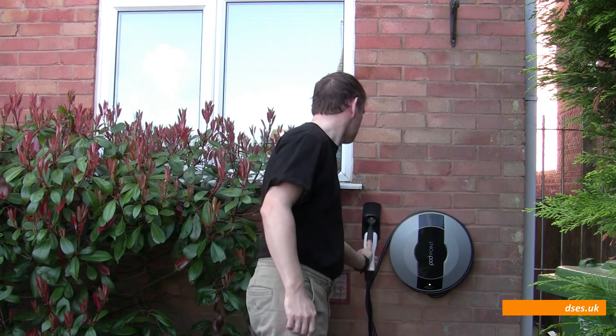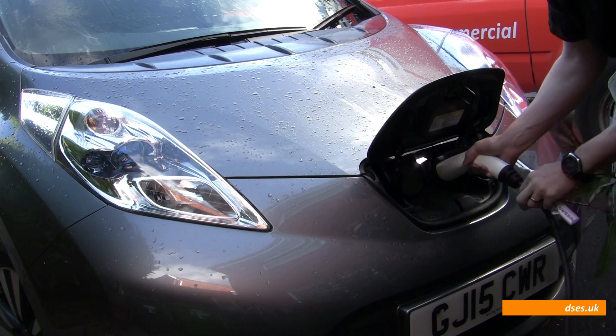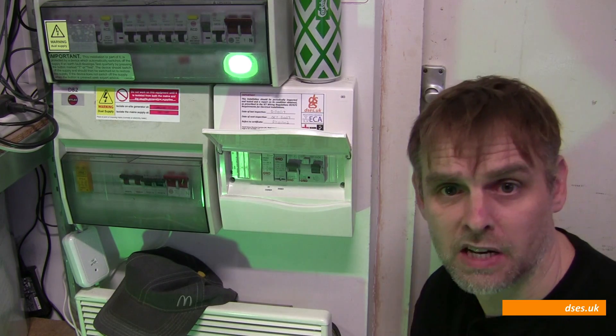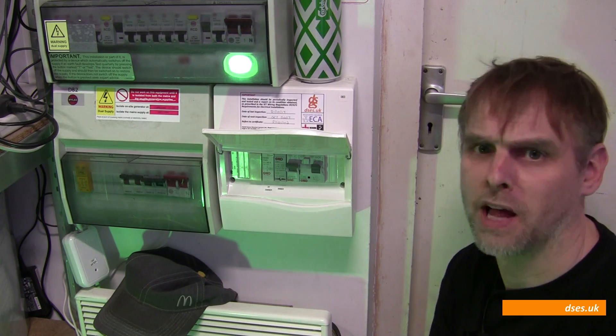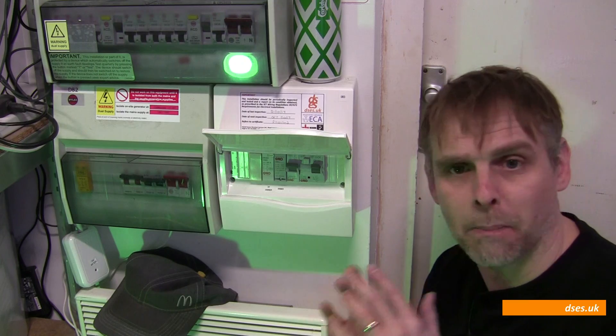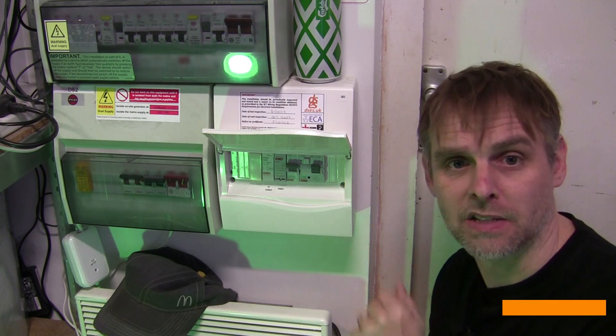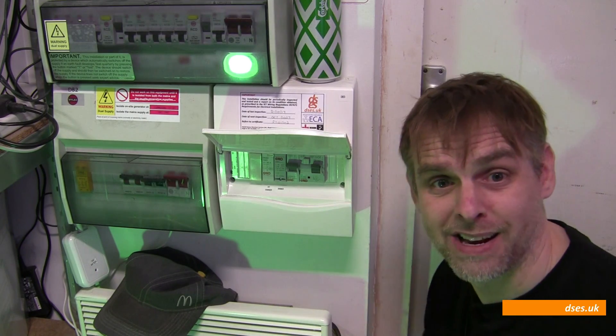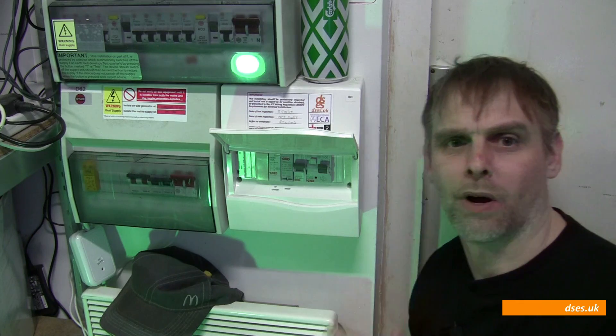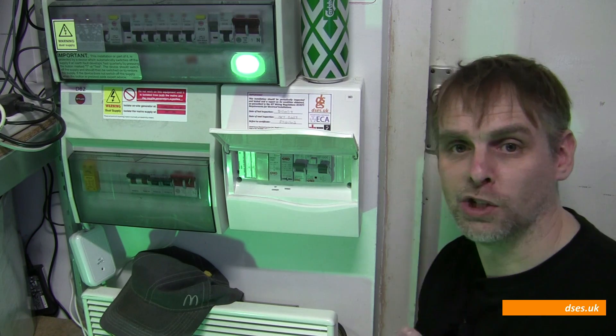This device doesn't just have to be for electric showers. I have one not because I have two showers but because I have an electric shower and an electric vehicle charging point and my cut-out fuse is only rated at 60 amps. The odds of these two appliances being on at the same time are low — the shower tends to get used mornings or evenings while the car is on charge in the early hours on Economy 7, or on a bright summer's day charged by my solar PV installation. However, as an installer I can't assume both won't be in use simultaneously, hence the steps I've taken. In my case the shower has priority. With the rise in car charging points, I think Garo are missing a trick by not marketing these in the UK as a solution for car chargers on installations where demand otherwise makes it difficult to justify the installation of a charger.